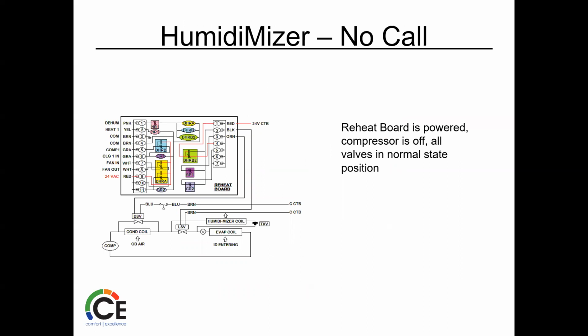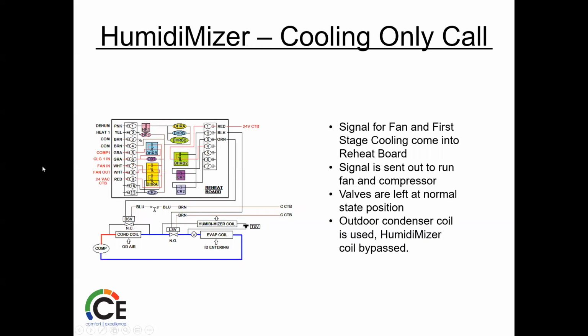So again, if we just want dehum, the reheat board is going to be powered, compressors off, all valves in normal state position. So we're just sitting there, showing you the normally open and normally closed options between those signals. We get a signal for fan, cooling call only, and first stage cooling comes in to the reheat board, signal sent out to run fan and compressor. Valves are left at normal state position. Outdoor condenser coil is used, HumidiMizer coil bypassed.